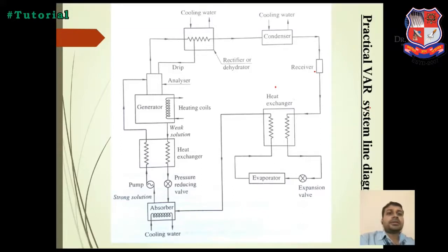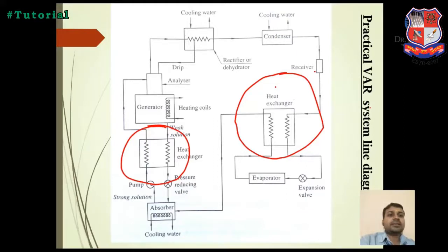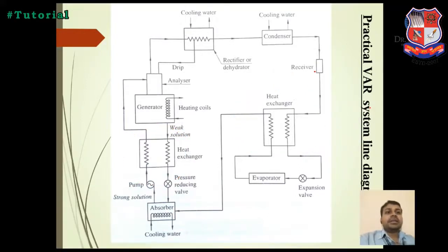Then the refrigerant is passed through the receiver. Here two heat exchangers are available. The first heat exchanger is between the expansion valve and the evaporator and absorber, and the other heat exchanger is between the generator and absorber. These two heat exchangers are used to increase the cooling capacity of the VAR system. For that we have to place two heat exchangers. The NH3 liquid passes through the receiver and then through a heat exchanger. From the heat exchanger the NH3 liquid passes to the expansion valve.